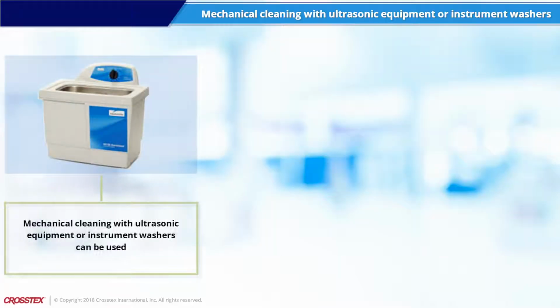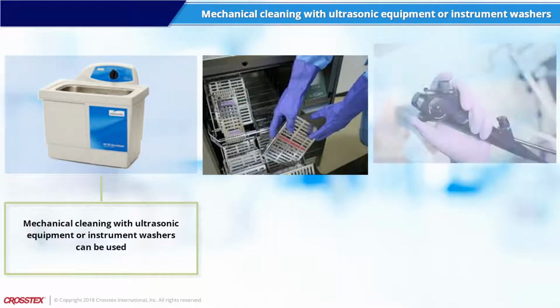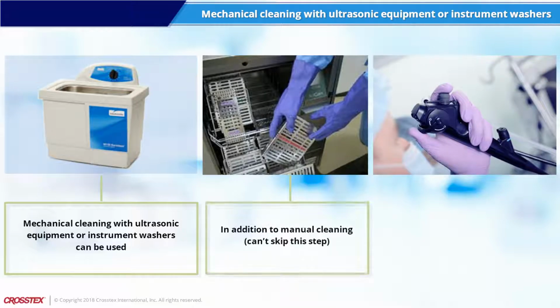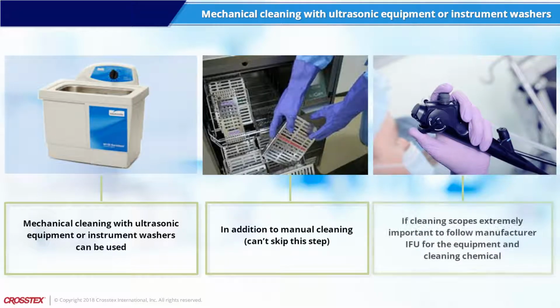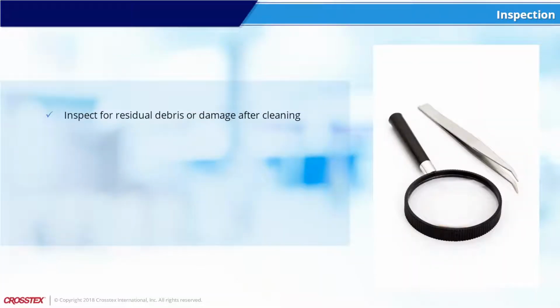Mechanical cleaning with ultrasonic equipment or instrument washers can be used in addition to the manual cleaning that was performed. If mechanically cleaning instruments or scopes, it is extremely important to follow the manufacturer's IFU for the equipment and the chemicals. Inspection. Each instrument should be critically inspected after each cleaning to check for residual debris or damage.